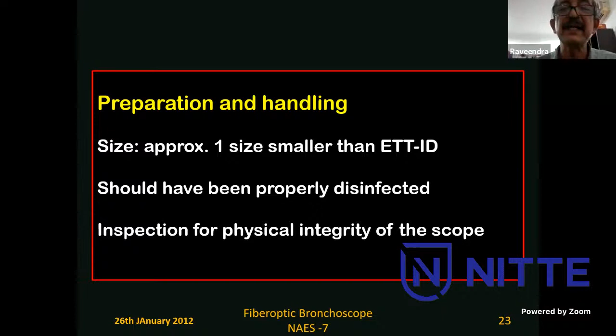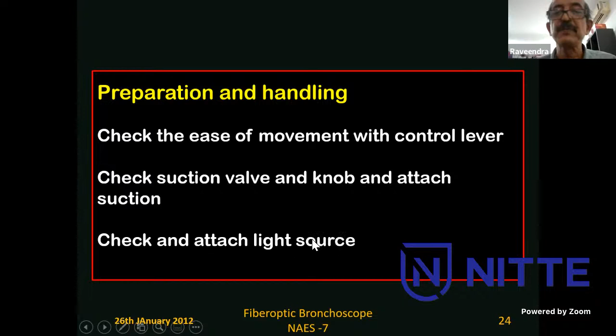So then check the ease of movement with the control lever. If it is not used for a long time, if the mechanical parts are not moving properly, then you may not be able to intubate smoothly. Then check the suction valve and the knob by pressing the knob and attaching the suction. Then attach and check the light source for proper working, and then focus if it is required.